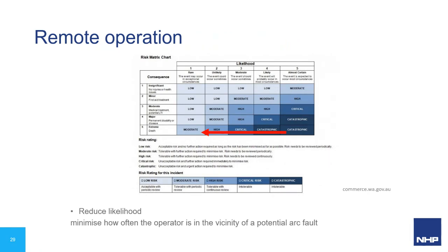So coming back to this risk matrix, I really wanted to address remote operation, which in 2020 should be kind of a norm. What remote operation does is it means we don't get any reduction in what we can do. So your throughput is all the same, but it reduces the likelihood that an operator's in that area. So that red arrow is moving directly to the left. You're minimizing how often the operator is in the vicinity of the potential arc fault. So it's an important move that you can make there.